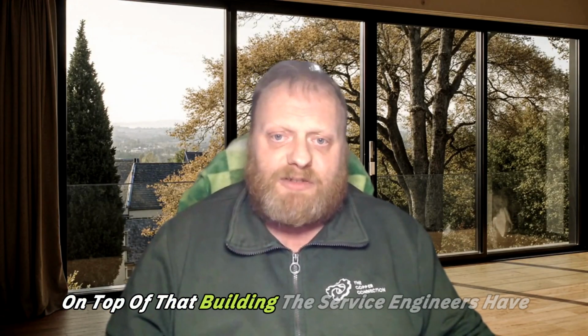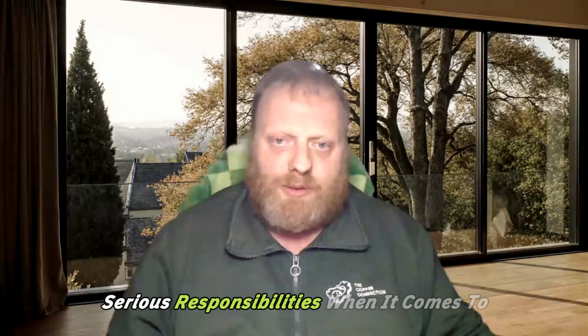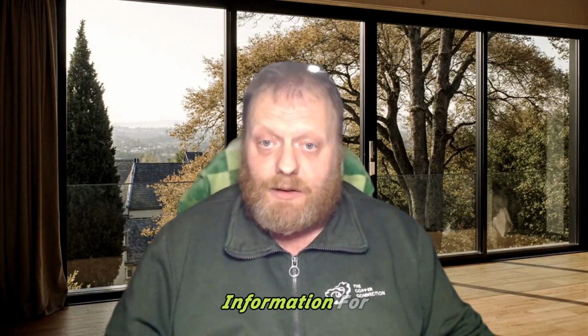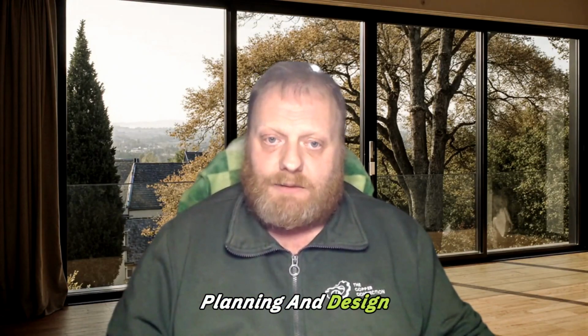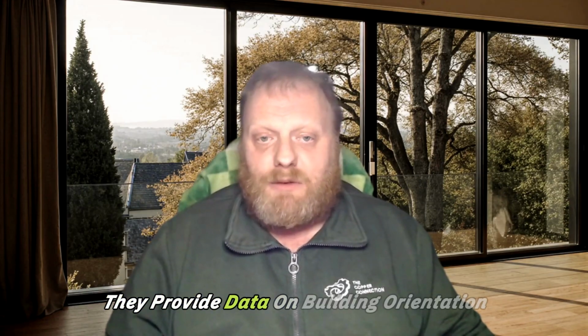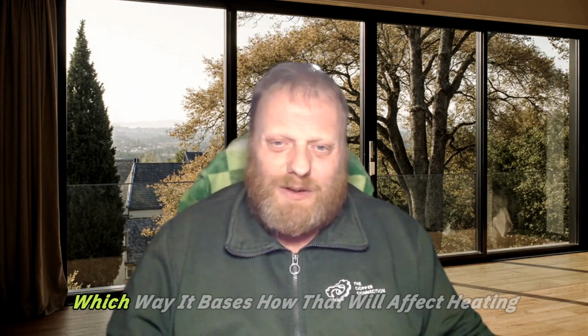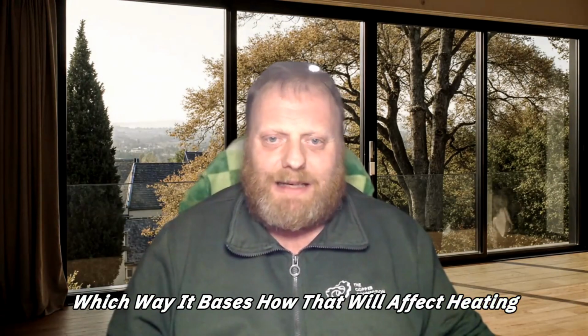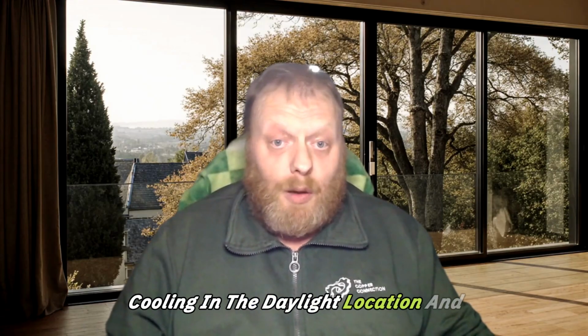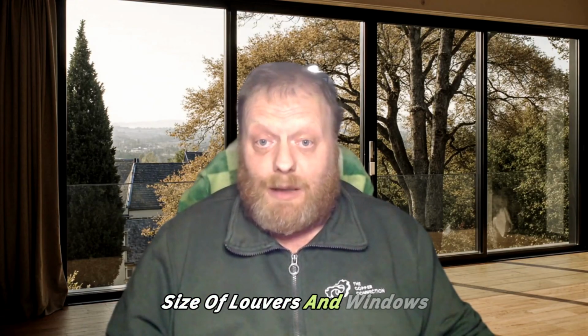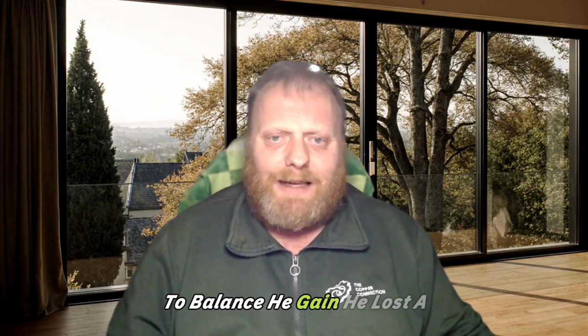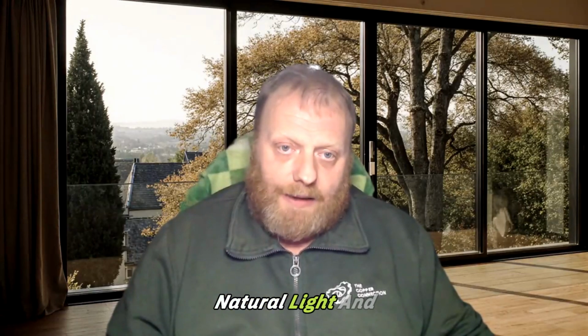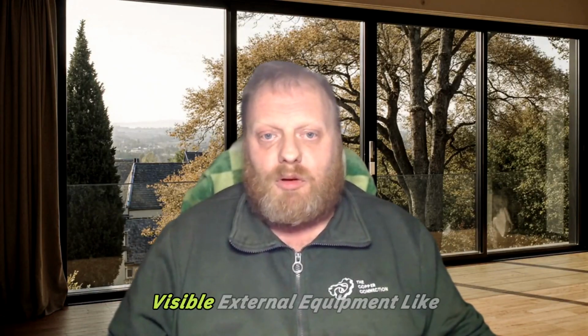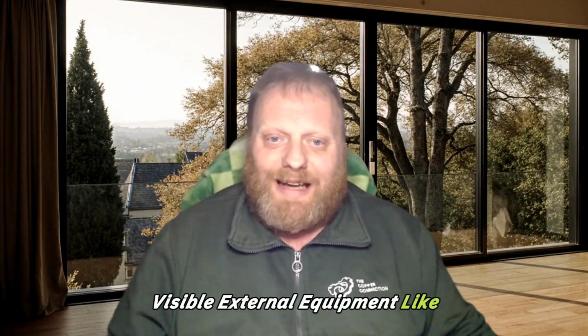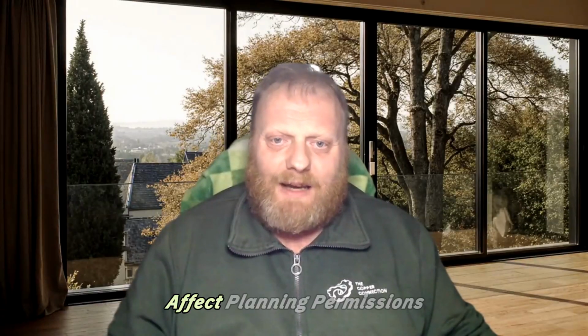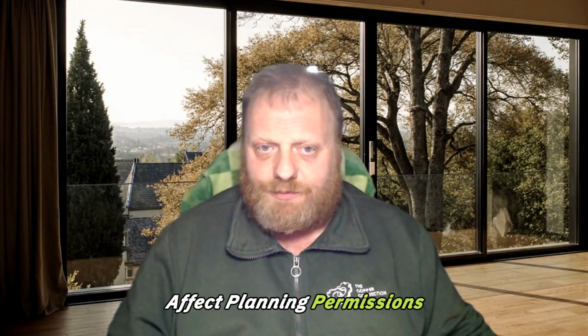On top of that, building service engineers have serious responsibilities when it comes to information for planning and design. They provide data on building orientation, which way it faces, how that affects heating, cooling and daylight, the location and size of louvers and windows to balance heat gain, heat loss and natural light, and the position of visible external equipment like chillers or flues that might affect planning permissions.